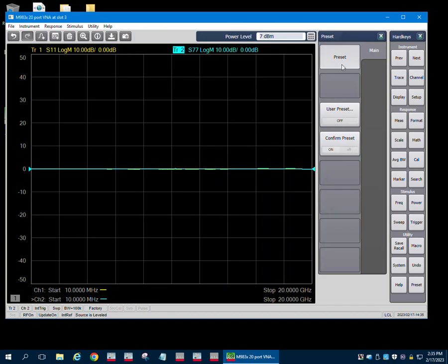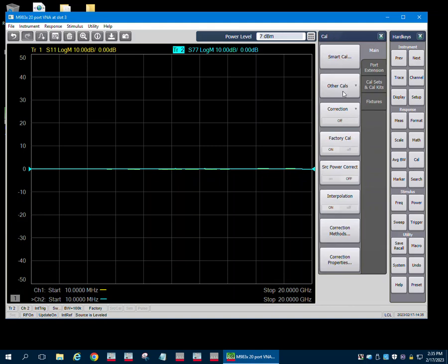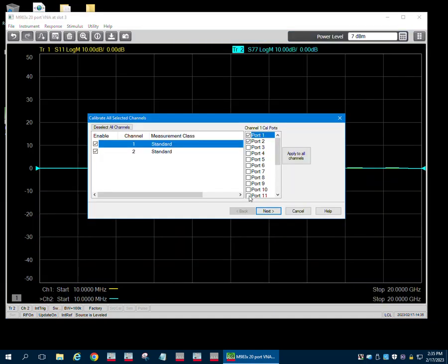But you just have to be aware that when you mix and match, you're getting different hardware specs, but they run as one network analyzer. You can calibrate them all as one network analyzer and so forth. There's no issue in calibrating it as one system.